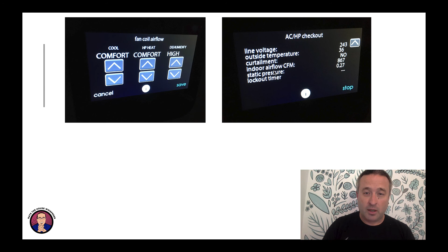I changed it to efficiency, and it got loud. Here's an important thing: if you don't understand this, when you get to the edge of what a duct system can handle and you push beyond it, your static pressure goes up really quickly. Note here, this is 867 CFM of airflow, and this is 1200, so it's only 38% more airflow, but it's 85% more static pressure. We go from 0.27 to 0.5, so we're almost doubling. We hit the wall here.